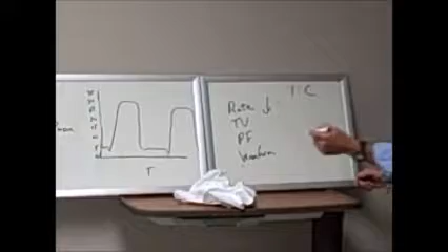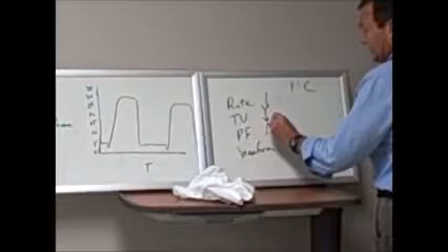What could you do to your peak flow? You want to deliver it faster to give them more expiratory time. So you want to increase your peak flow. Again, the trade-off for that is a higher peak inspiratory pressure, because we're in IMV with a tidal volume at this point. What could you do for your waveform to give them more expiratory time? Square. That's right. It's delivered faster.